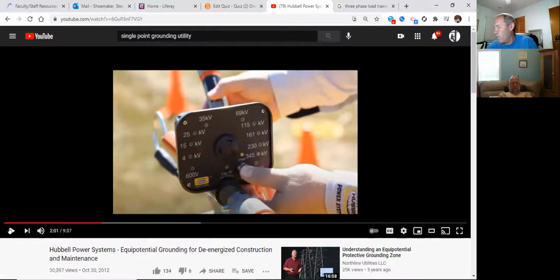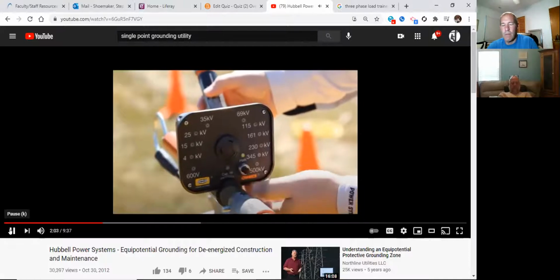Yeah. We actually don't even need to be up in the air to do this. We can do this on an extension stick. So we can use a voltage indicator, a hot horn or a tick tracer, to see if there is presence of voltage on their line. They're doing the same thing with this stick right here, except that's a very, very expensive stick. A tick tracer is going to run you right around 25 bucks. This is probably about what, Robbie, 300-400? Probably so. Yep. A separate instrument tester, as must be done prior to every use.